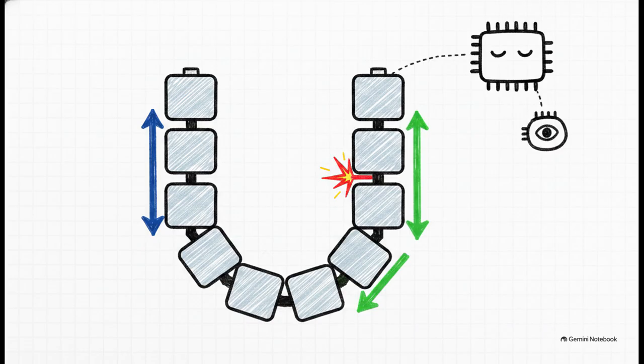Because communication here is entirely bidirectional, the host can choose to send messages north up the stack or south down the stack. Why does that matter? Well, imagine a wire snaps from heavy vehicle vibration or a connector fails mid-pack. The system instantly detects the fault and just reverses its communication direction to reach those stranded devices from the other side. It ensures no cell ever goes unmonitored, which is absolutely crucial for preventing fire risks.